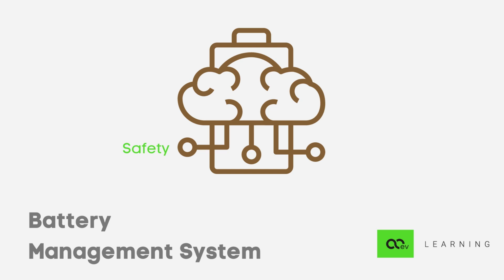First is safety. BMS controls all the functioning limits of the pack, electrically as well as thermally. Electrically means over voltage and under voltage. For a 48 volt nominal system, the higher side will be 54.6 volts and the lower side will be 39 volts. Thermally means the operating temperature between 15 to 35 degrees Celsius. BMS is critical to accident prevention.